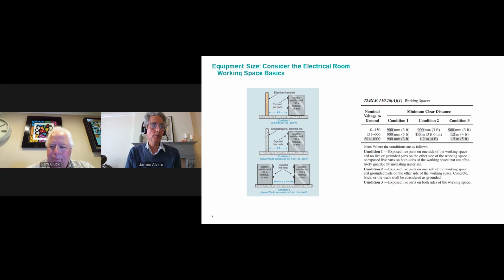So for instance, if you look at the table, you can see that for a 120/208 board with the picture above, you need 3 feet in front of, let's say, a standard drywall, 3 feet in front of a concrete wall, even though it's grounded, typically, and 3 feet in front of another 120/208 board. However, if you go to 480 and read across the table, it becomes 3 feet, 3.5 feet, and 4 feet. And then it gets a little bigger if you're at 601 and above. So those working spaces are important.